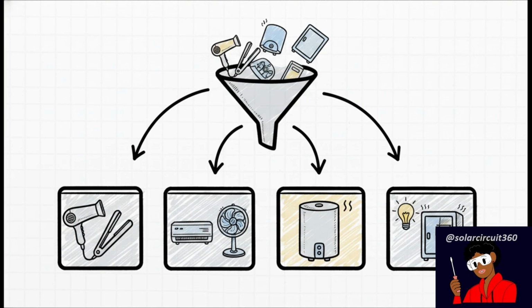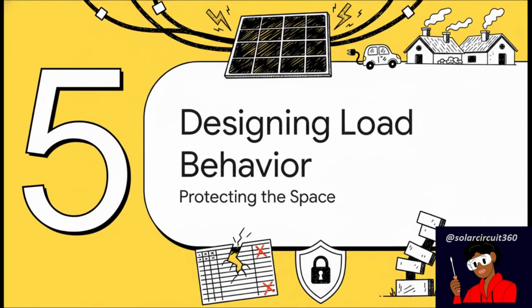When you're structuring a salon's diverse loads, you have to categorize them precisely. Group them into heat styling loads, climate control loads, water heating loads, and then your general service loads, like overhead lighting or sterilization gear. Once you break the whole place out like this, you can finally apply accurate diversity factors and duty cycles to each specific group, instead of lazily treating the entire salon as one giant, continuous, monolithic power draw.